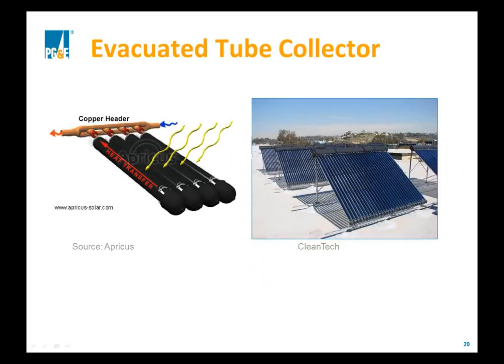And then evacuated tube collectors, we also see quite often. These are vacuum tubes, so they're providing insulation. They're also oriented in such a way that they're collecting as the sun moves throughout the sky on these cylindrical absorbers, and heat is transferred up to a header pipe, which is where the heat transfer fluid, which supplies the heat to the solar storage tank, travels. These are able to generate even higher temperatures than glazed flat plate collectors, and certainly than unglazed. They're often used in very cold climates, both because of their insulative capacity and because, as you can see in the picture, they allow snowfall in particular to pass through. So in climates where there's snow, these can be a good solution. Next slide.